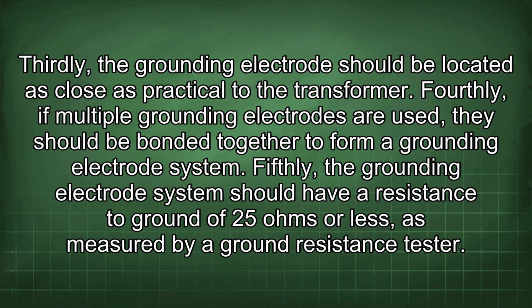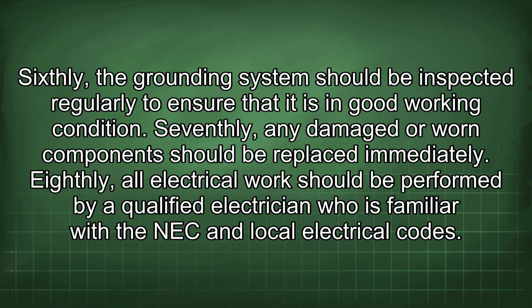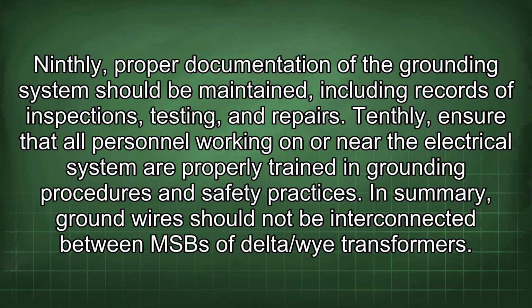Fifthly, the grounding electrode system should have a resistance to ground of 25 ohms or less, as measured by a ground resistance tester. Sixthly, the grounding system should be inspected regularly to ensure that it is in good working condition. Seventhly, any damaged or worn components should be replaced immediately. Eighthly, all electrical work should be performed by a qualified electrician who is familiar with the NEC and local electrical codes. Ninthly, proper documentation of the grounding system should be maintained, including records of inspections, testing, and repairs.